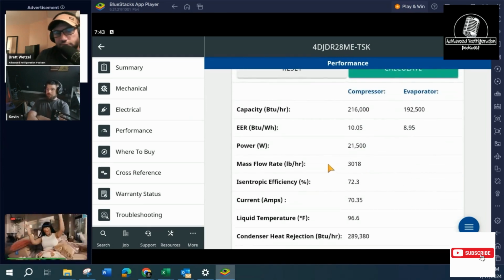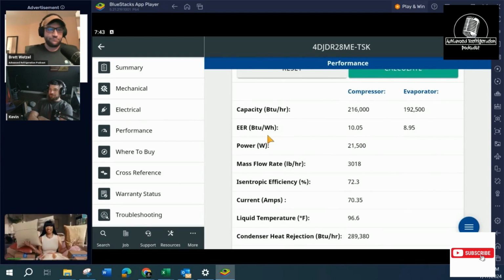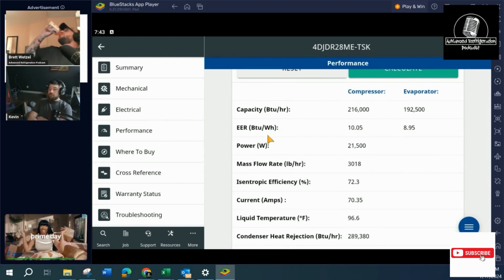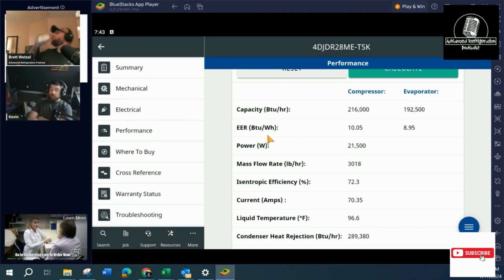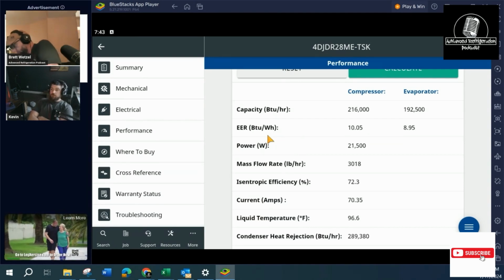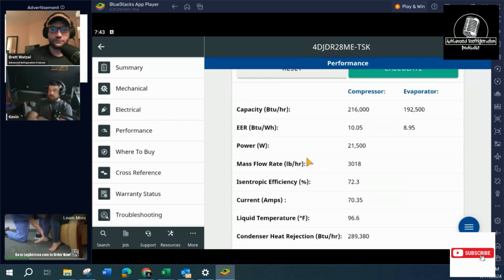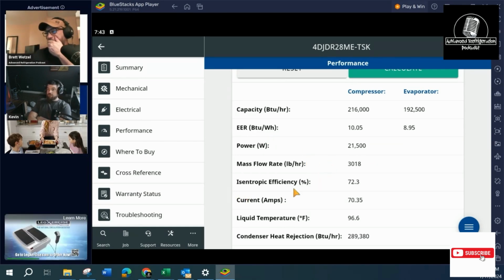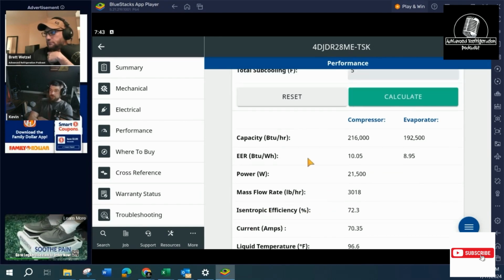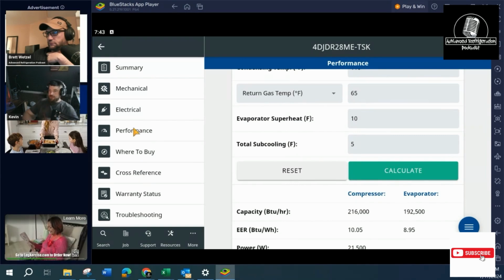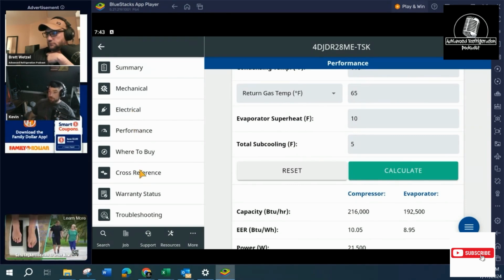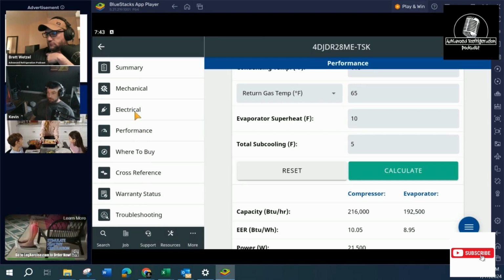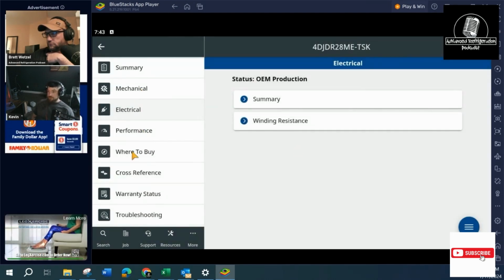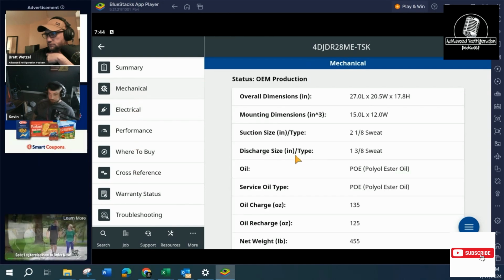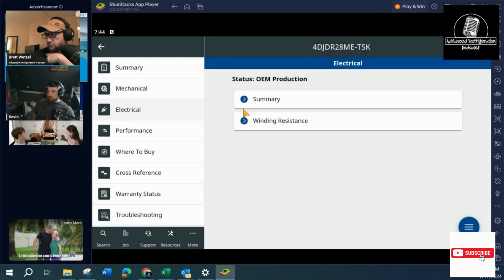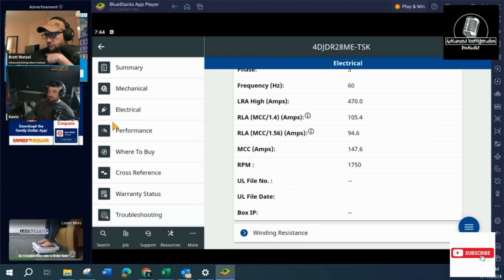Now, what Brett and I were trying to articulate in our enamored state is the fact that if the compressor was down a piston or had a valve issue and it was running the plus 25, it should be running at 70.35 amps. If it's drawing 69 amps or like 60 amps, something's wrong with the compressor. And that compressor would probably pass the pump down test. If the end bell's not hot, it'll probably pass that pump down test. Now, if it isn't hot, most guys will say, do the pump down test. I've been burned by it so many times that this is how I test all my compressors.